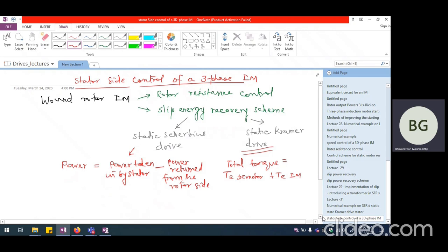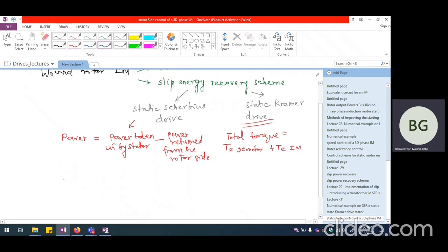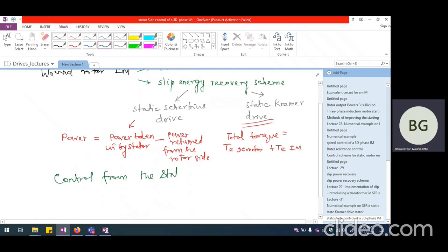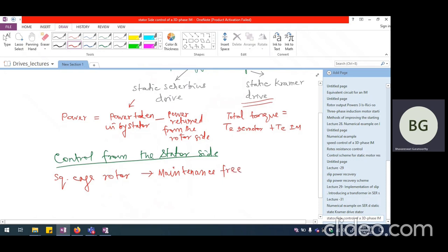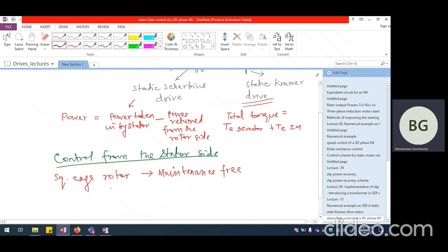Slip power recovery is applicable only to wound rotor induction motor. If we are looking at control from the stator side, this is applicable to both wound rotor as well as squirrel cage induction motor. But primarily we talk about squirrel cage induction motor here because they are completely maintenance-free. So when we talk about stator side control, we mainly talk about squirrel cage induction motor.